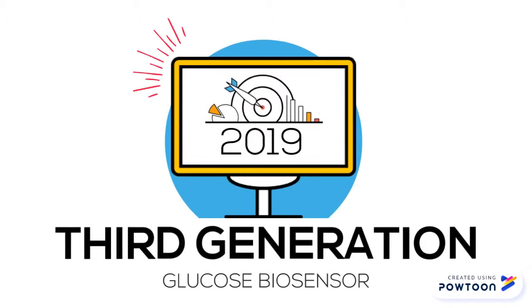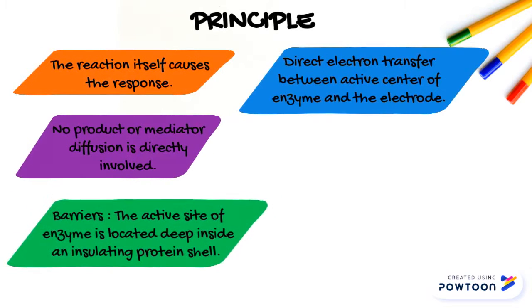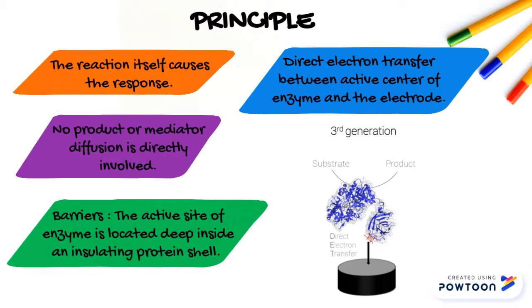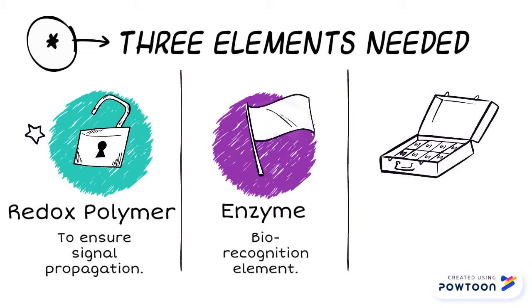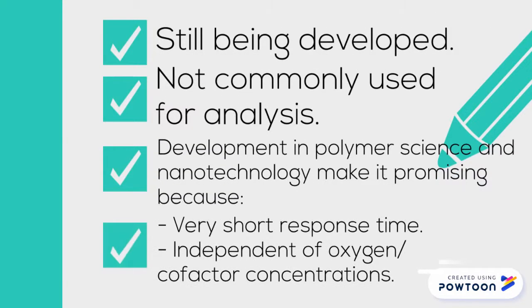Third generation biosensor: the reaction itself causes the response and no product or mediator diffusion is directly involved. It is based on the direct electron transfer between the active center of the enzyme and the electrode. This is difficult because the active site of the enzyme is located deep inside an insulating protein. Generally, the third generation biosensor consists of three elements: the redox polymer, the enzyme, and the electrode. These biosensors are still being developed and are not commonly used. However, developments in polymer science and nanotechnology make third generation biosensors promising, as they are likely to have very short response times and be relatively independent of oxygen or cofactor concentrations.